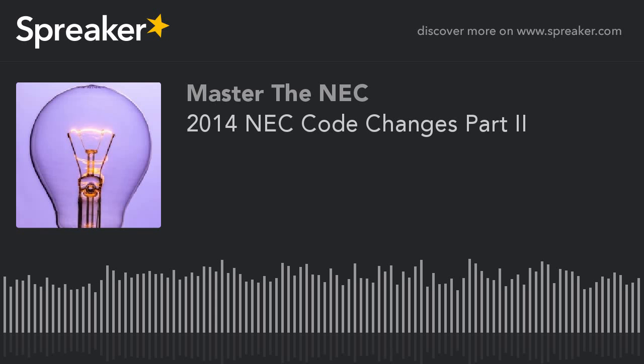Okay, so this is a new addition to the 2014 NEC. And if you read it, and I'll read it exactly how it says it in the NEC, and again, if you got your code books, you might want to give it a look. It's 210.8A9. And it says, bathtubs and shower stalls, where receptacles are installed within 6 feet of the outside edge of the bathtub or shower stall, is going to require GFCI protection on those receptacles.